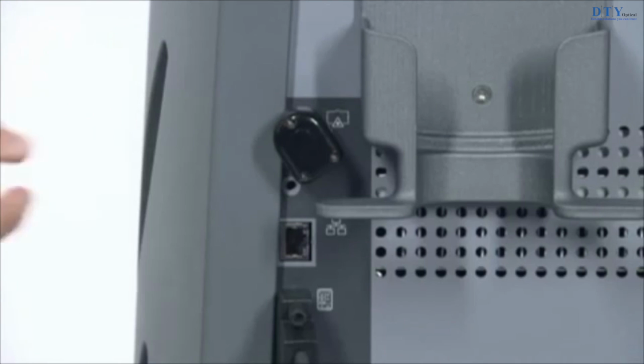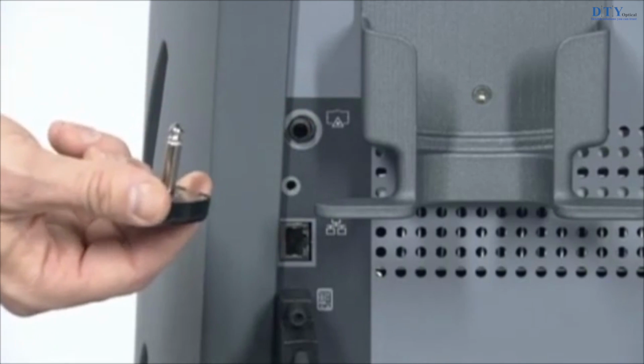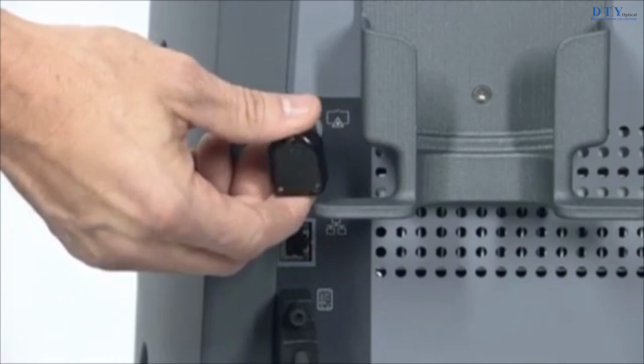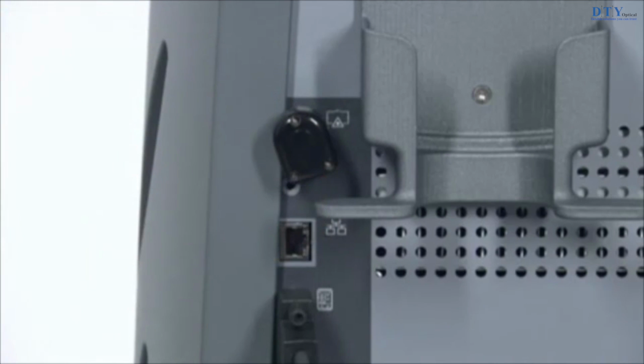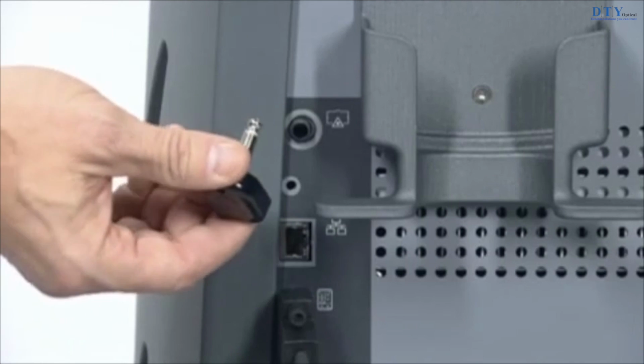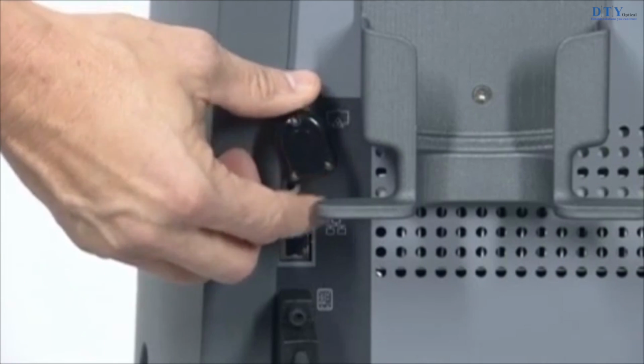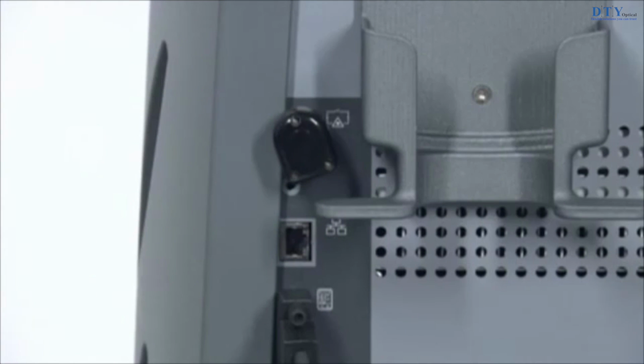The external door interlock is a safety feature that disables the laser if the treatment room doors are opened or the interlock plug is removed. Use of an external door interlock is optional. However, you must insert the interlock plug into the interlock receptacle whether or not you are using an external door interlock. The laser remains inoperative until the plug is inserted into the receptacle.